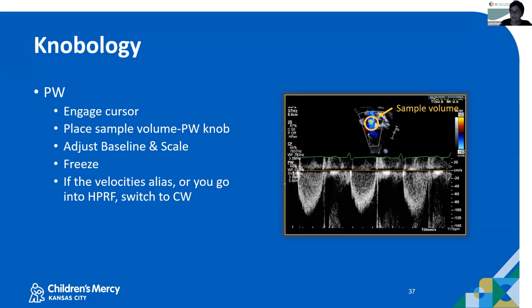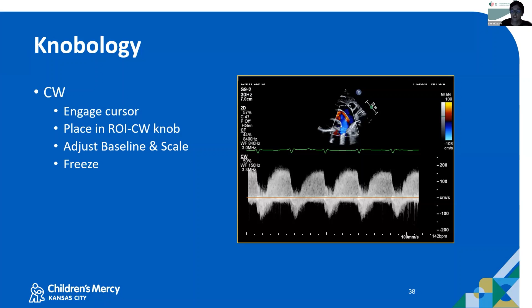So continuous wave, again, you engage your cursor, you're going to place it in your region of interest, you're going to hit your continuous wave knob, and your Doppler is going to start scrolling. Adjust your scale and baseline. You can use iScan and it will adjust your scale and baseline for you. It's just personal preference. When you see 3 or 4 waveforms go by that you like, usually your sweep speed's 100 because of pediatric heart rate, you're going to freeze and hit acquire.